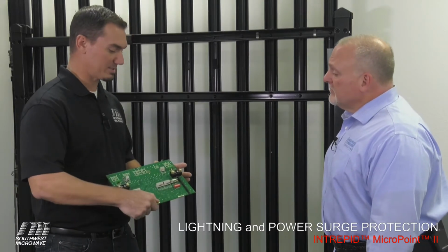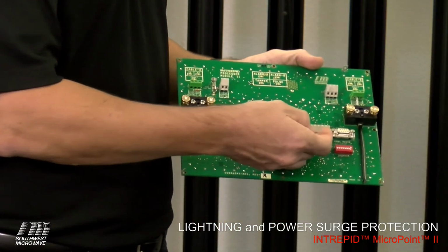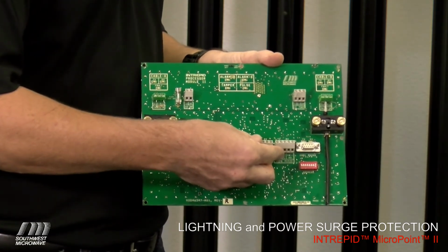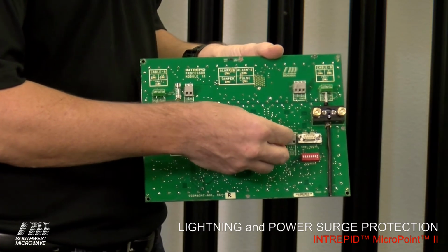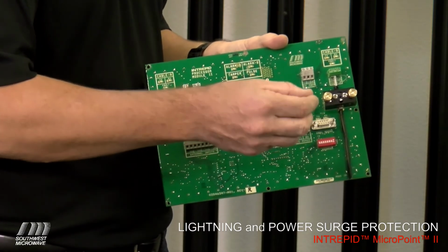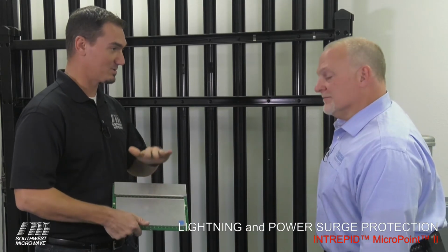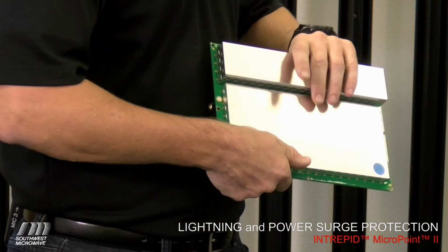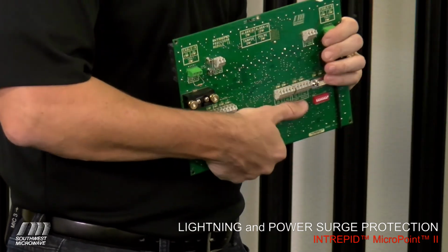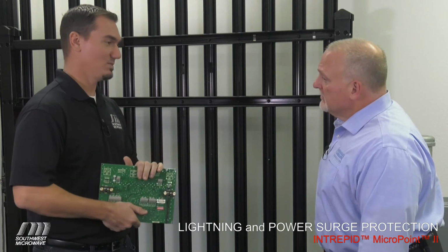With the MicroPoint system, we've pulled the processor out of the box so I can show you what we've got going. Right off the bat, we've got our input comm lines. These two communication ports are optically isolated. This optical isolation allows data to pass through optical bursts, and prevents any electronic interference, voltage, or current from passing from the lines onto the board itself. Second, all of the components are surface mounted and protected in these shield cans. So these boards are pretty robust. Not only have we taken those precautions, but we also conformal coat the board, so I can handle this without worrying about EMI, RFI protection just as we stand here. So right off the bat, we're safe that way.